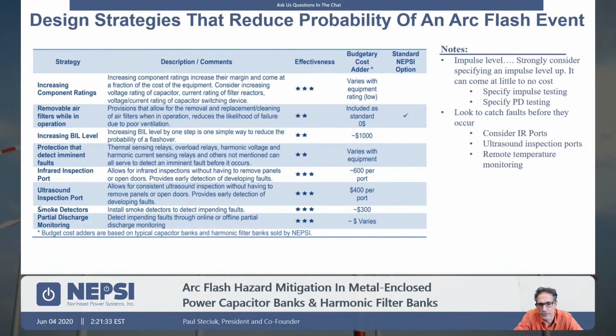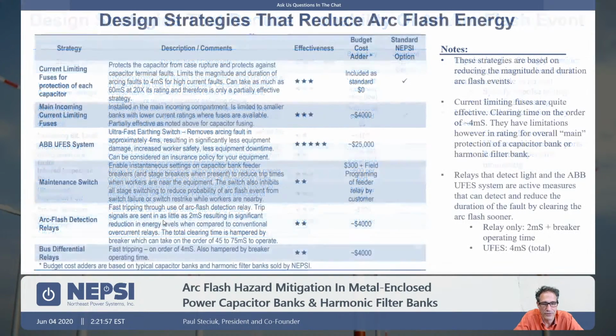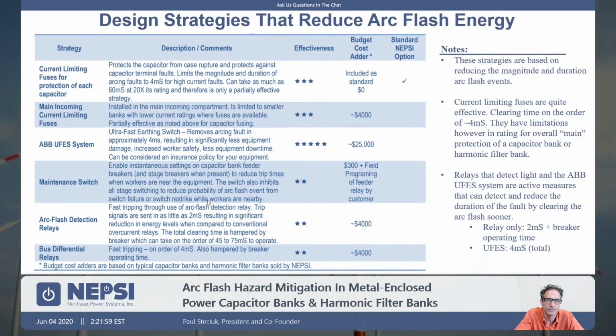So there are some active maintenance type devices you can look at. One is ultrasound inspection ports, and this is to monitor for partial discharge within the equipment, corona discharge, and you can also do partial discharge monitoring devices that you can install. These things can have a significant cost, these online partial discharge monitors. Smoke detectors, if you have a fire, it's nice to detect it early and take it offline.